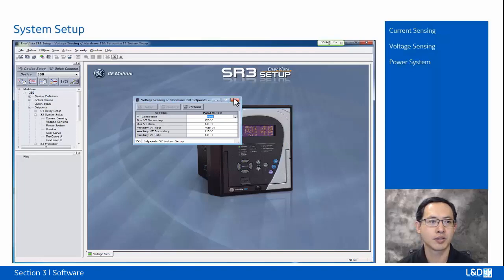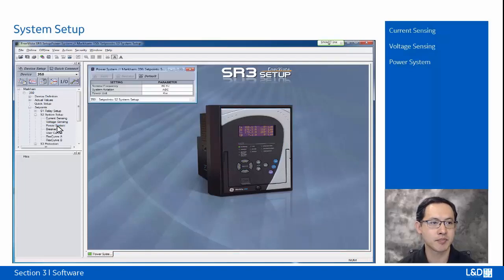And under the power system, we can set the nominal frequency to be 60 Hz or 50 Hz. And then we can choose the phase rotation to be ABC or ACB, and also we can select the power unit, kilowatts or megawatts. And that's the setup of the system setup.